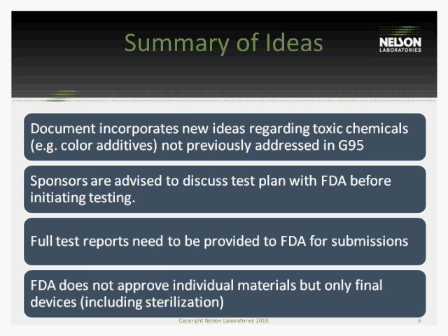I'm not saying that can't be successful, but you really have to evaluate what processing you're doing to those materials in your final device. So is there any kind of molding that could involve mold release agents, or sterilization that can have an impact? Specifically, gamma sterilization tends to have a big impact potentially on biocompatibility. So just because your raw materials have good information doesn't necessarily mean that you can eliminate all your biocompatibility testing.